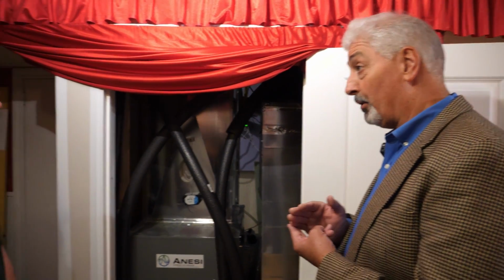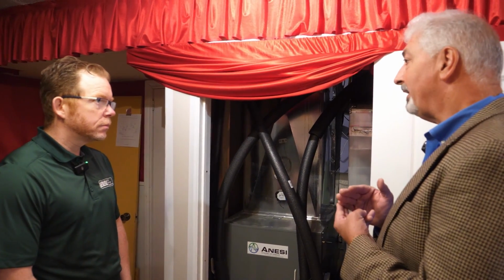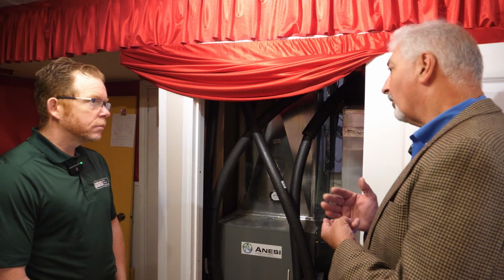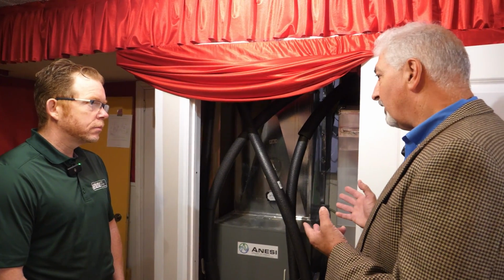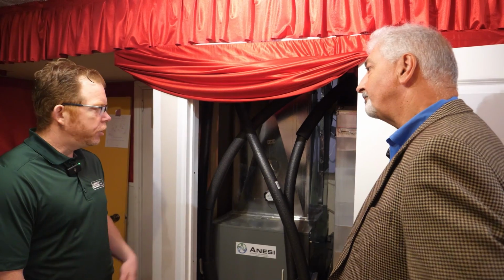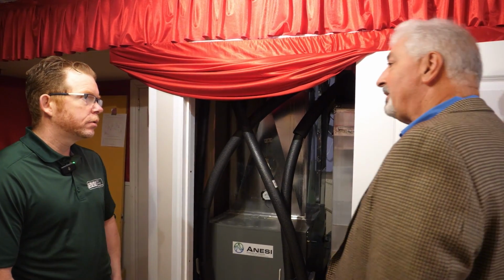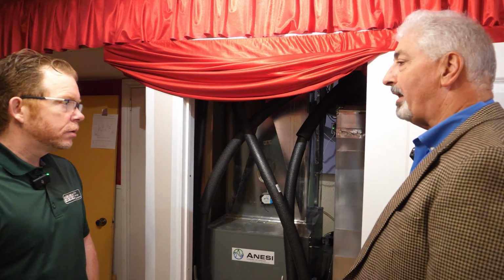We are talking about a gas heat pump that's located outdoors, so you're keeping all of your combustion, all of your refrigerant outdoors. The only thing brought in is the 40% propylene glycol food grade hydronic solution. It's got an inhibitor in it, basically for the benefit of the gas heat pump outdoors. So it's very, very safe. Right. Okay. Now, are you guys supplying the propylene glycol, or are they getting that from their own source? We will be supplying propylene glycol to the reps, and the reps will supply it out to the contractors.